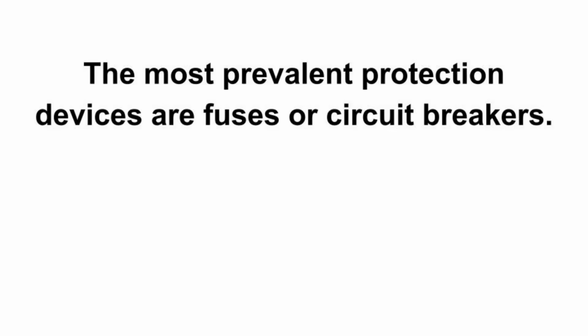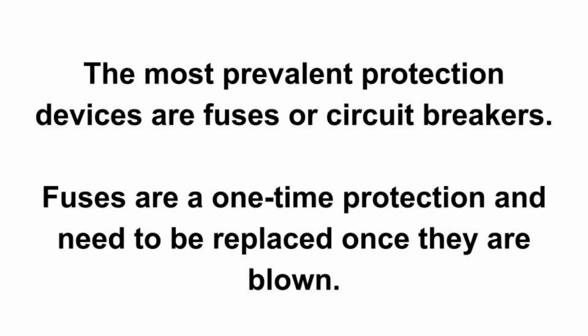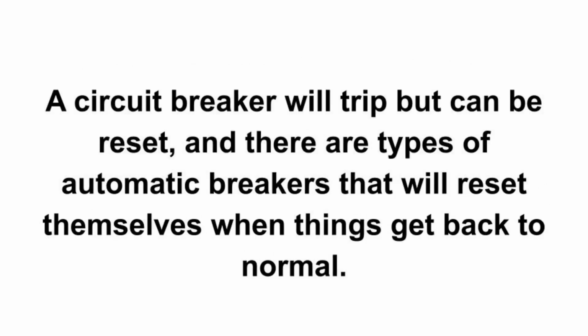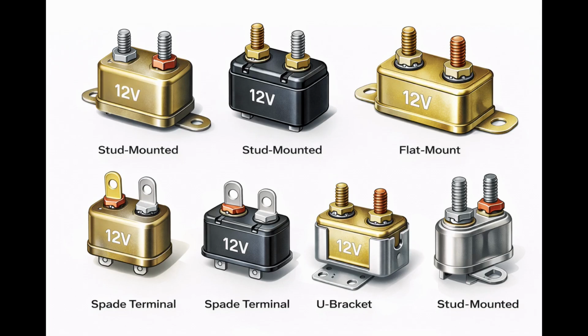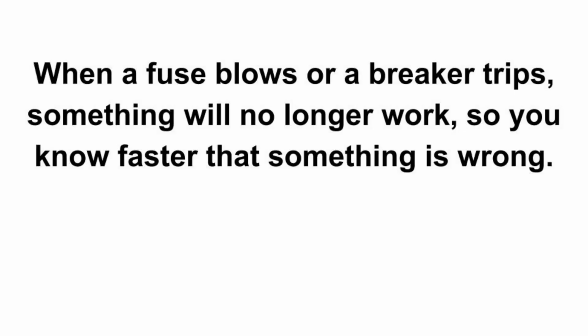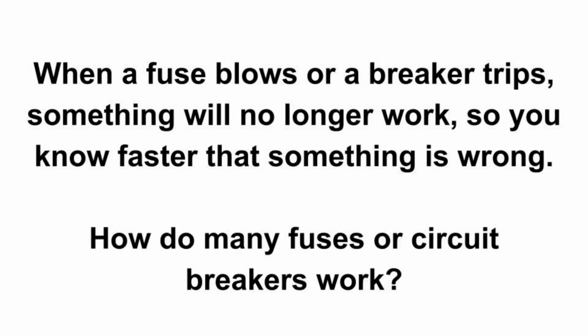The most prevalent protection devices are fuses or circuit breakers. Fuses are a one-time protection and need to be replaced once they are blown. A circuit breaker will trip, but can be reset, and there are types of automatic breakers that will reset themselves when things get back to normal. I would not recommend the auto reset type, as those might trip and reset many times before you know there is a problem. When a fuse blows or a breaker trips, something will no longer work, so you know faster that something is wrong. How do fuses or circuit breakers work?